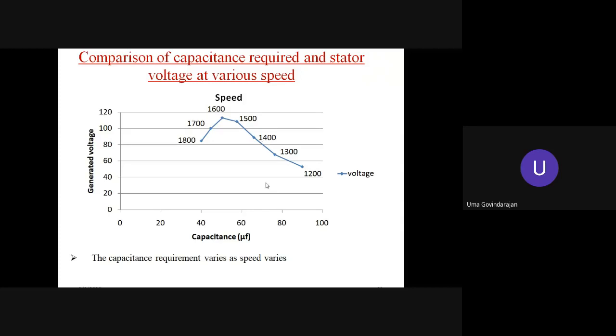Even if other speeds are available, if the speed varies to 1300, then I have to use an 80 microfarad capacitor. So practically it is not possible to switch the capacitor over the entire range. You can go for one optimum capacitor value, and the additional VAR requirement you can supply via some power converter. That's to make you understand that the capacitance requirement varies as the speed varies.